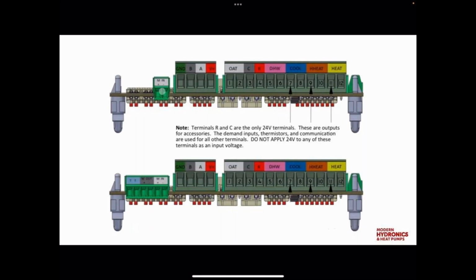And it's probably kind of hard to see on the screen here, but this little green connector is labeled as M in, and that is for a modulating signal input. This is where you would hook up a third-party control to cascade these heat pumps. So we can receive a 0 to 10 signal from a third-party control, something like an HBX Eco 600 or a tekmar control. There are various controls on the market, but we can receive a 0 to 10 signal into this port to cascade multiple of these units together. And it will kick on the backup as needed, whether it's electric backup.